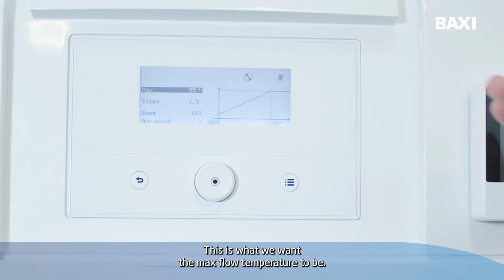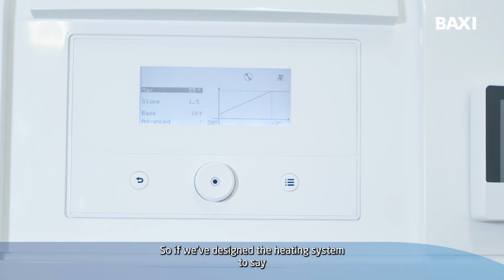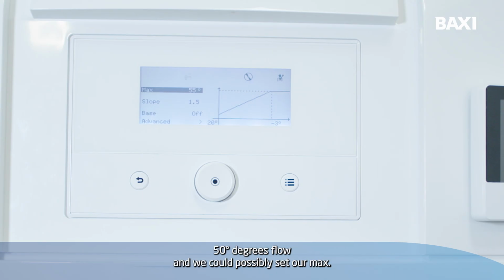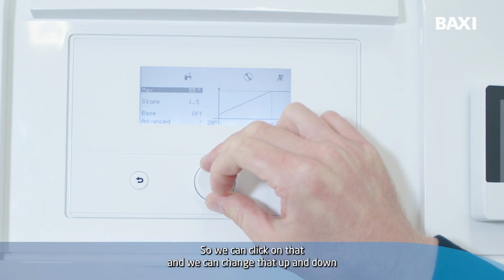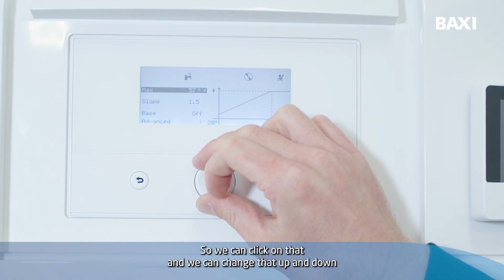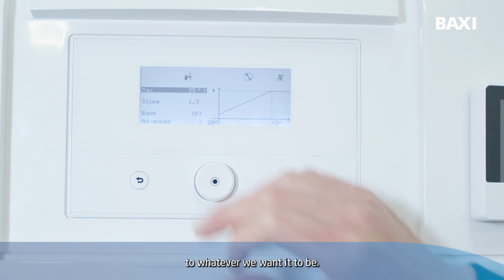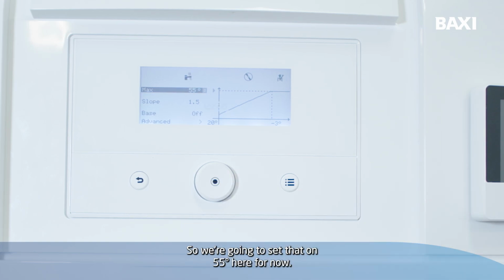This is what we want the max flow temperature to be. So if we've designed the heating system to say 50 degrees flow, then we could possibly set a max flow temperature to 50 or even 52, 53, which would mean it would give us more heat if it got colder than what our outside design temperature was. So we can click on that and we can change that up and down to whatever we want it to be. So we're going to set that on 55 here for now.